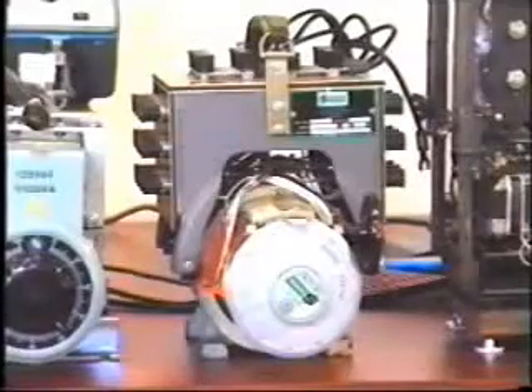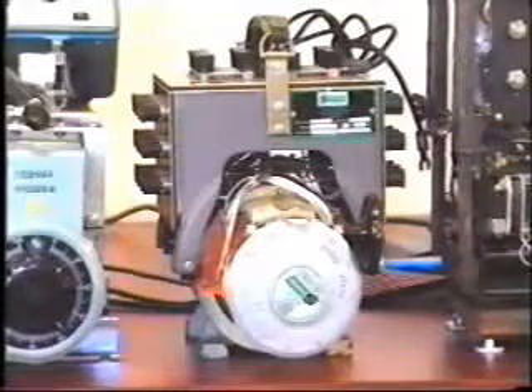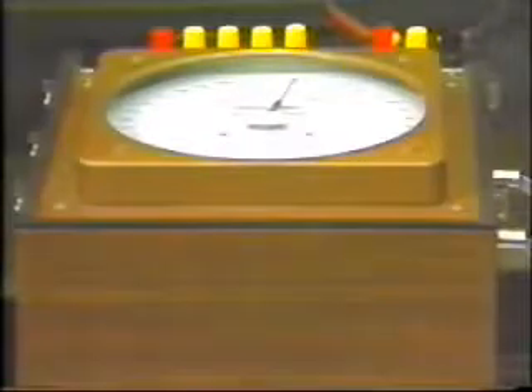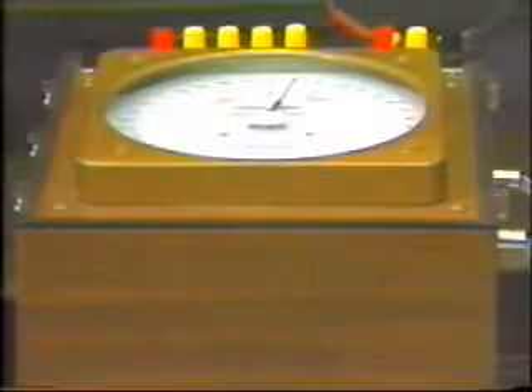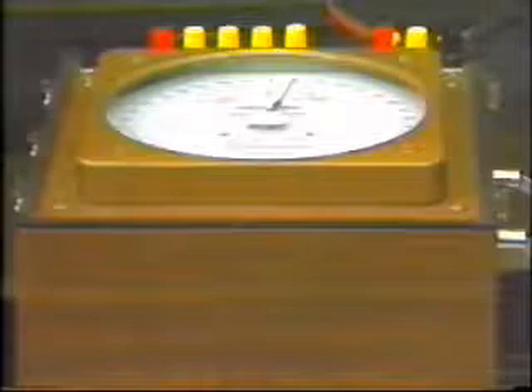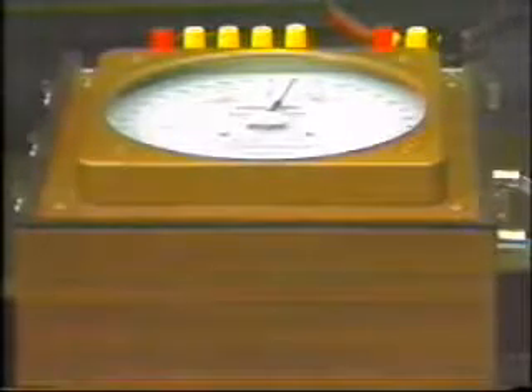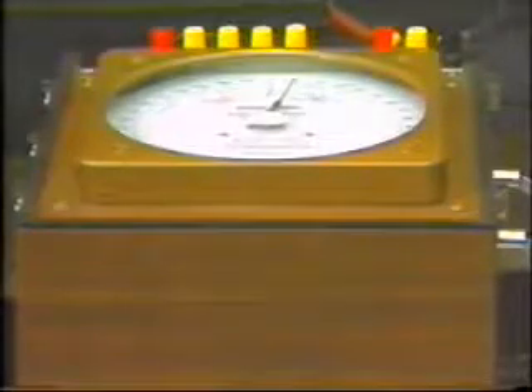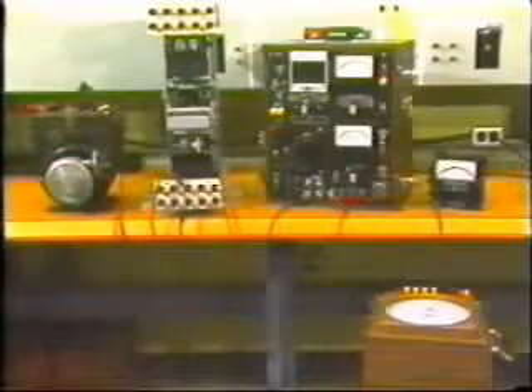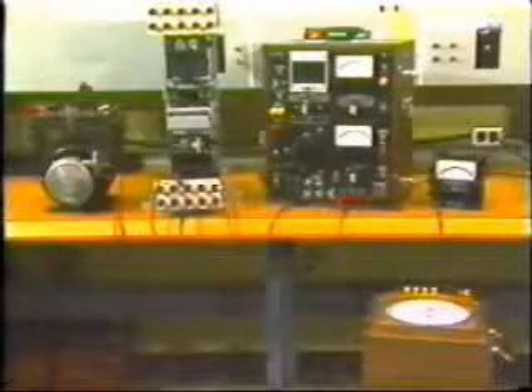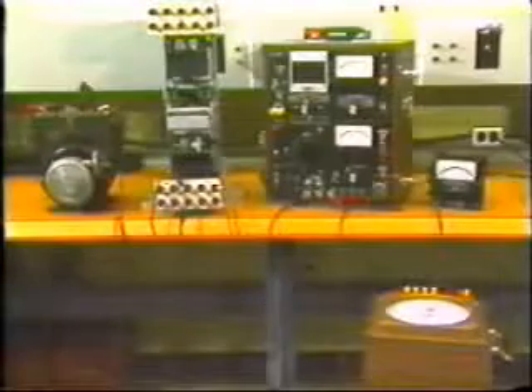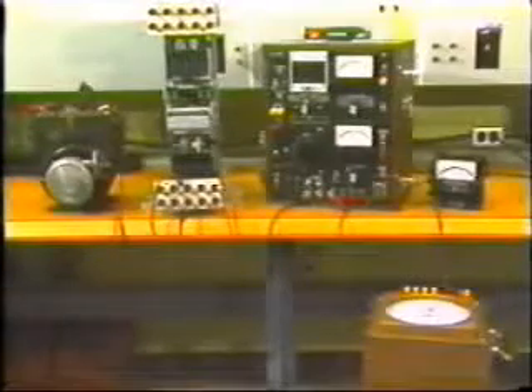Phase-shifting transformers require a three-phase input to operate. The phase angle meter's inputs are isolated from each other, so at least with this instrument, we don't have to worry about reversing ground connections and causing short circuits. However, we must observe proper test polarities so that the relay doesn't see quantities 180 degrees out of phase from what it expects. We've just been looking at the traditional type of test signal sources.